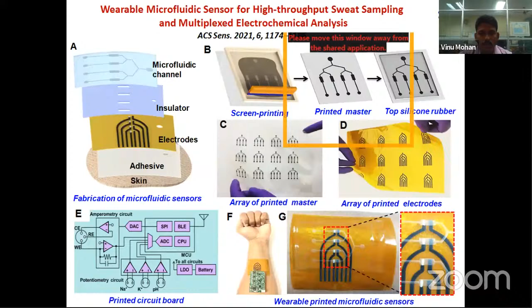So all these analytes are really important. Our main challenge is that the lactate sensor uses amperometric detection, and the other ions use potentiometric detection. When we apply potential for amperometric measurement, the current definitely flows through the non-selective electrodes for potentiometric detection. So there will be current interference from the amperometric sensor.